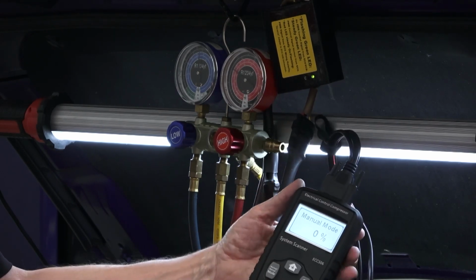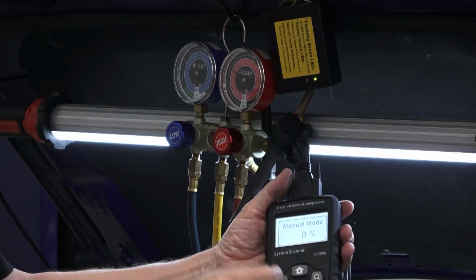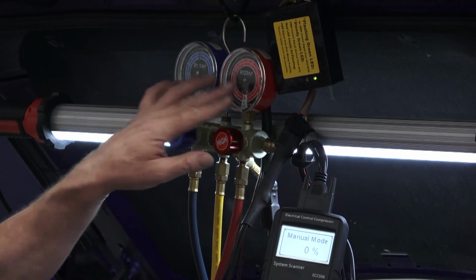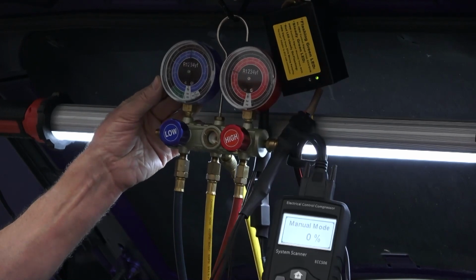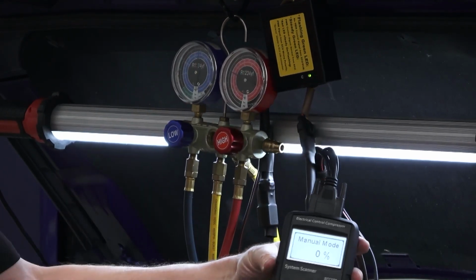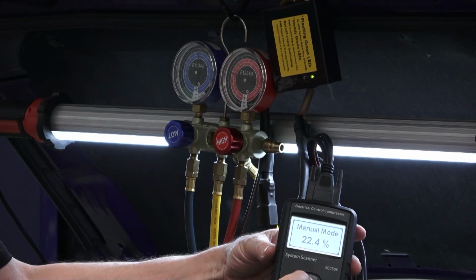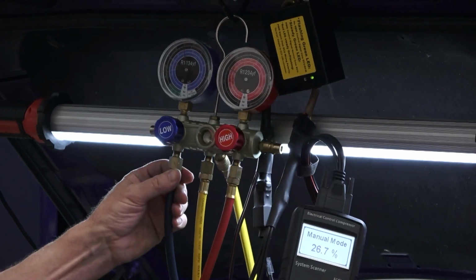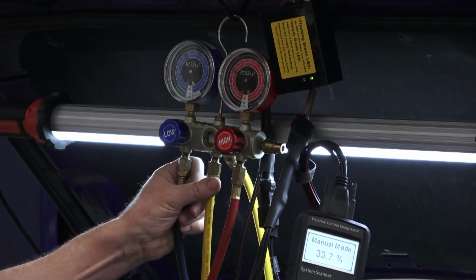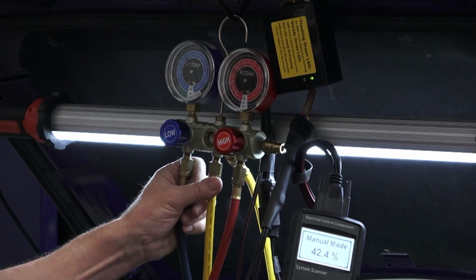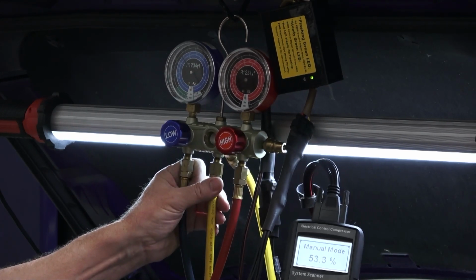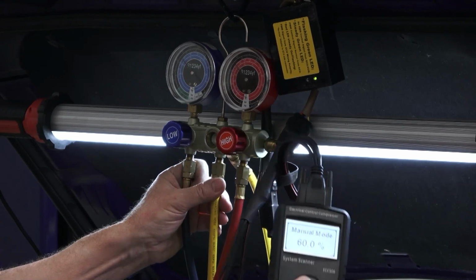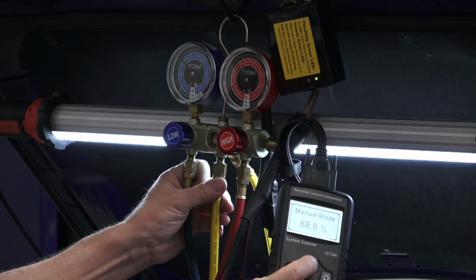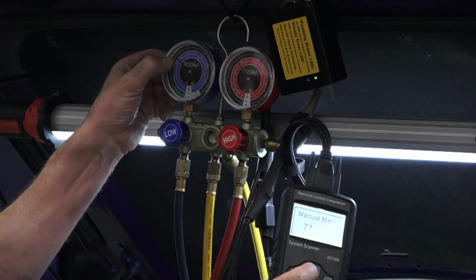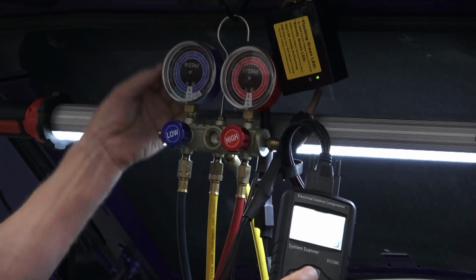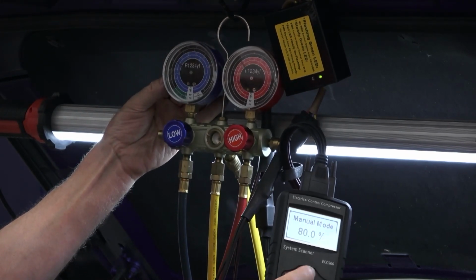In other words, I'm going to use the tool to send the duty cycle command to the solenoid, and I can watch on my pressure gauges to see, does the pressure actually change? So I'm going to start increasing the command, and watch very carefully: you see the low side pressure starting to come down, and the high side pressure starting to increase. At 53%, 55%, you can see the duty cycle command increasing here, the low side pressure dropping, and the high side pressure starting to increase as I change the command to the solenoid.